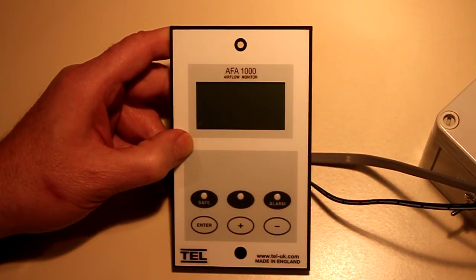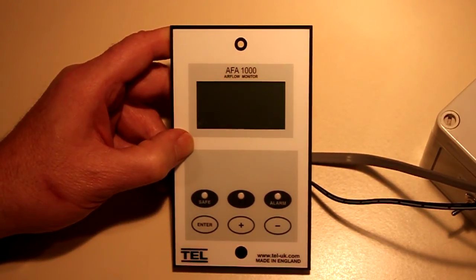The TEL AFA 1000 is a state-of-the-art digital fume hood monitor that works on the principle of measured face velocity using a through-the-wall hot wire sensor. The AFA 1000 is password protected to prevent tampering and has a series of screens guiding the operator through the calibration process. In this video, we will demonstrate the straightforward calibration and operation process of an AFA 1000.